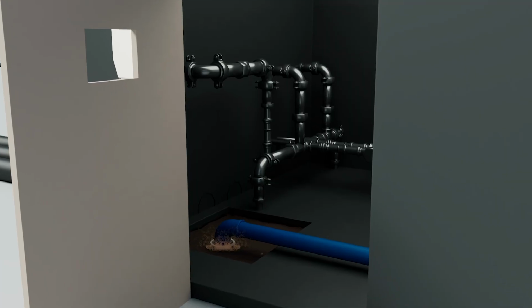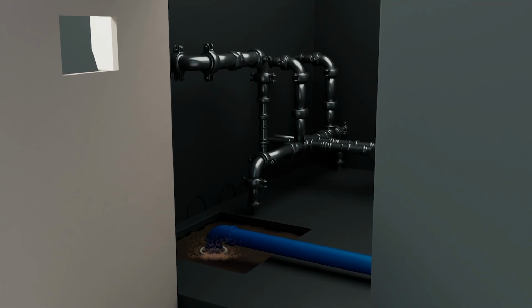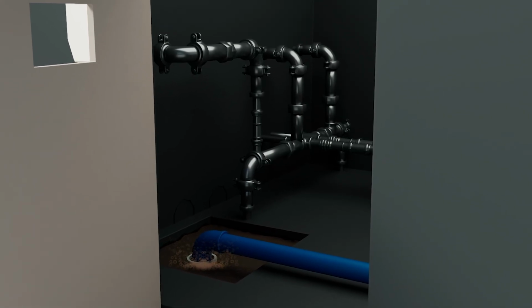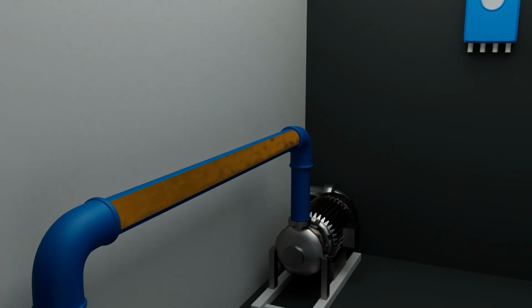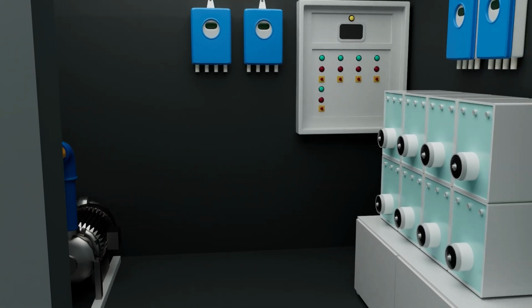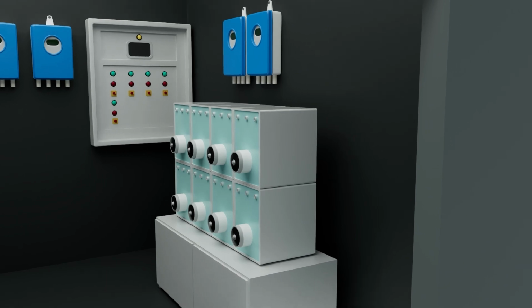The discharge valve automatically shuts off when either the booked volume or the discharge time is completed, whichever occurs first. This prevents hydraulic shock loads at the CETP inlet. SCADA has installed auto samplers for sample collection, ensuring compliance with CETP inlet norms through regular daily collections.